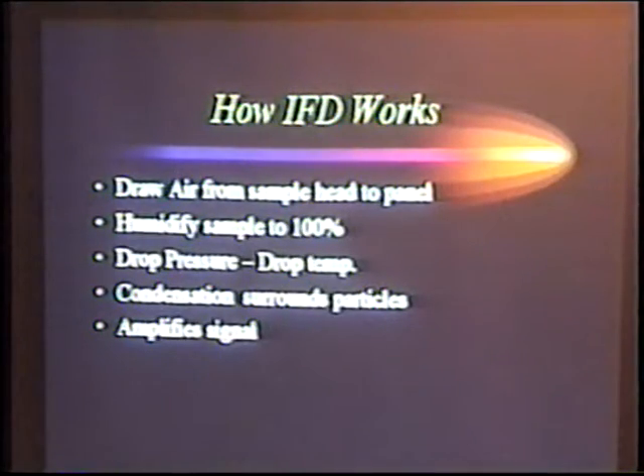Next question I'm asked quite a bit is, well, if it's invisible, Brian, how do we see it? How do we detect it? And how do we use it from a detection system and release it for a reaction, or sprinkler, or whatever you're going to do with it? Well, how an IFD works, and IFD stands for incipient fire detection, or incipient fire detector: it's a control panel mounted on the wall. We have an air sampling head out in the field somewhere, ceiling, subfloor, maybe an air conditioning unit, HVAC unit. We draw air from the sample head back to this control panel.